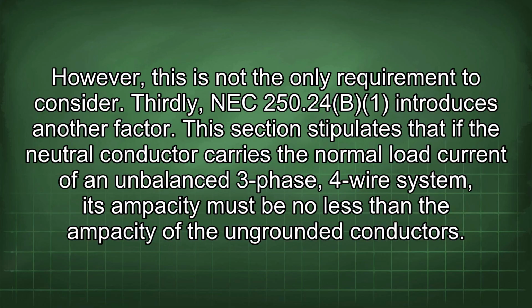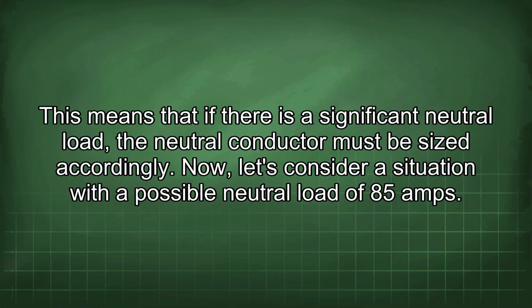This section stipulates that if the neutral conductor carries the normal load current of an unbalanced three-phase, four-wire system, its ampacity must be no less than the ampacity of the ungrounded conductors. This means that if there's a significant neutral load, the neutral conductor must be sized accordingly.